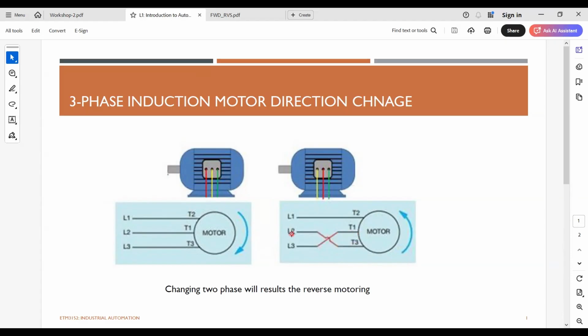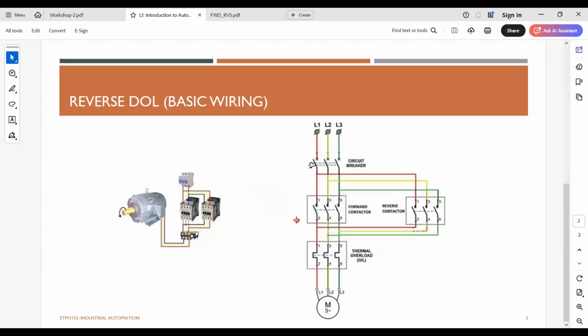Here, L2 is now connected to the terminal 3 of the motor, and L3 is connected to the terminal 1 of the motor. So that swaps 2 terminals of the motor, which results in a change in the direction of the rotation of the motor. Similarly, you can do it for any 2 wires, then you can get the same result.